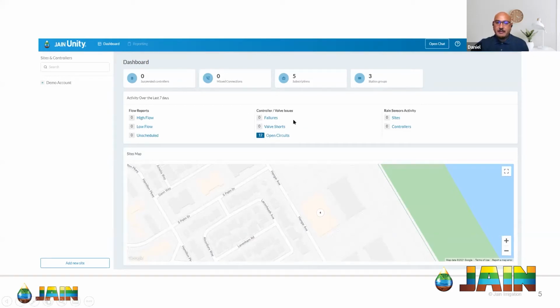Other thing here, controller valve issues. If you have a failure, if our controller has a bad component inside, maybe a base module or a triac board, could be a bad modem in there. Doesn't happen too often, but we alert you, hey, there's a problem with your hardware. Let's get out there, take a look at it, as well as valve shorts.